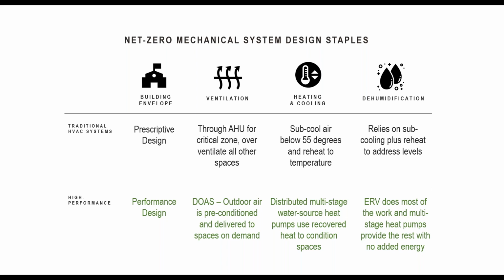A more traditional approach might be with a VAV system, you're going to cool a space. Well, you've got to cool it even beyond the 55 degrees that you're probably going to serve the space at, and then you got to heat it back up with reheat. It's kind of like driving down the road with a foot on the gas pedal and on the brake pedal at the same time. It makes no sense.